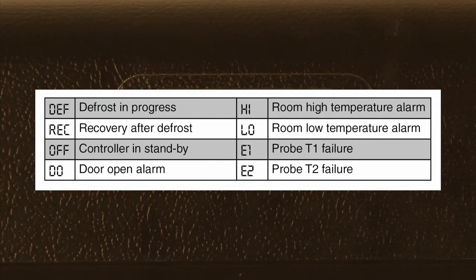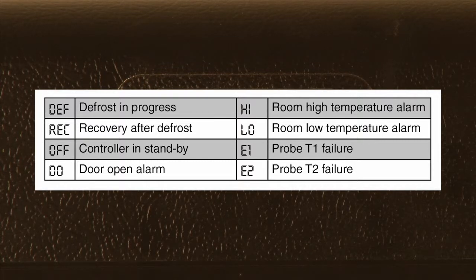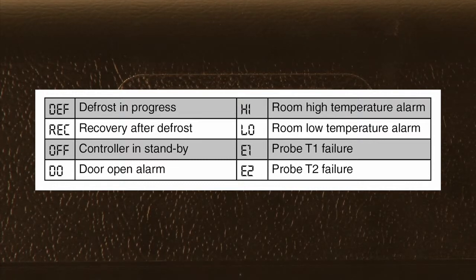Should there be a wiring problem or a functional failure of either of the two temperature probes — one mounted on the evaporator coil, the other in the return air stream of the cabinet — you would see E1 or E2, indicating an alarm function for a temperature probe failure.